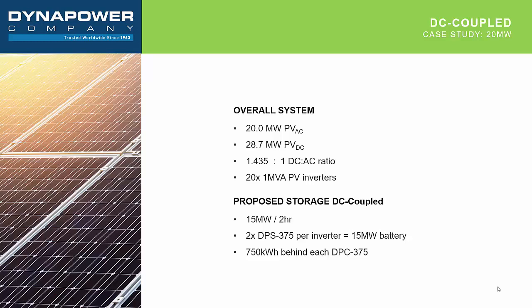So we've done a number of studies looking at different existing and new configurations. Let's take a look at one that represents a typical retrofit application. In this case, again, it's a 20 megawatt PV array, oversized though, so it has a 1.435 DC to AC ratio.